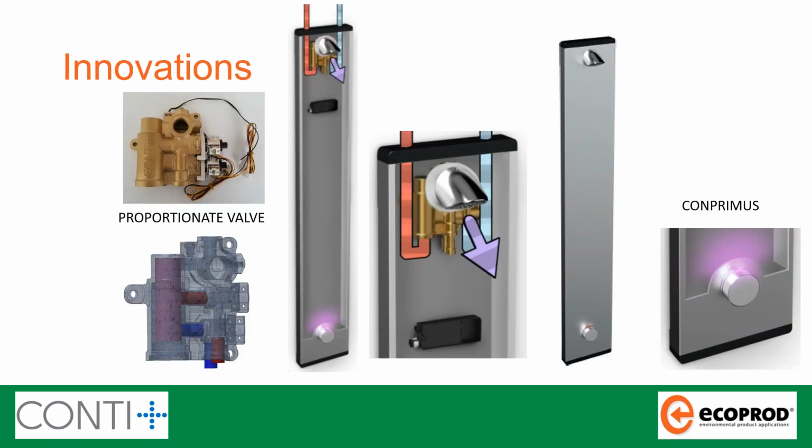Conti Plus is also recognized for innovation. And a couple of images here show a couple of things. First of all, on the left, we have what's called our proportionate valve, which we hope to bring to the market later this year. The proportionate valve has been designed to mitigate any redundant pipework where mixed water may sit. So you can see on the second image the proportionate valve is actually located directly by the shower outlet itself. Therefore, once water is mixed within the valve, the amount of dead leg to the shower head is less than an inch. And again, you can just pump through on a regular basis with Hygiene Flush, so avoiding stagnating water completely.